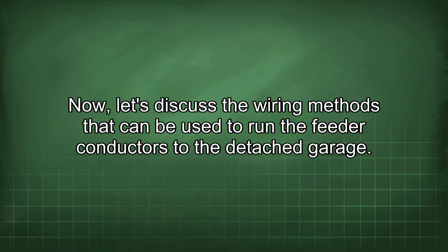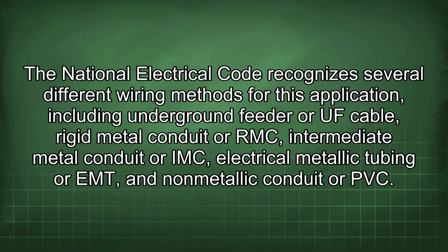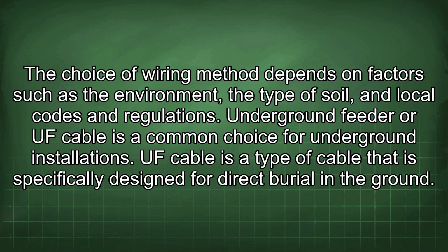Now, let's discuss the wiring methods that can be used to run the feeder conductors to the detached garage. The National Electrical Code recognizes several different wiring methods for this application, including underground feeder or UF cable, rigid metal conduit or RMC, intermediate metal conduit or IMC, electrical metallic tubing or EMT, and non-metallic conduit or PVC.